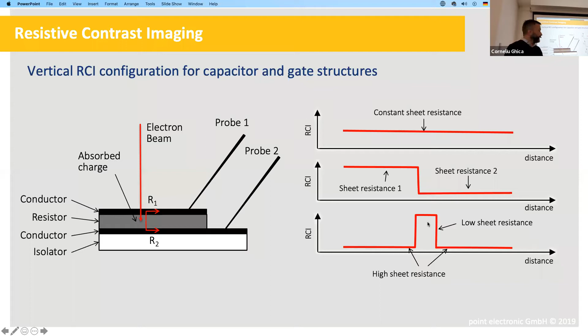So if we build an image and the capacitor is underneath this structure here, and there is one probe connected to the metal layer underneath, and another probe connected to the metal on the top, we get a bright spot where this leaks. And in this example, using the electron microscope as a tool to localize things is even more important, because if you try and turn on this capacitor, it has a leakage, so it will produce a local melt zone, it will blow up. And once you have a melt zone, there is no chance of discovering what was there originally, what caused that melt. So this is a very great low power technique to localize weakness in oxides.